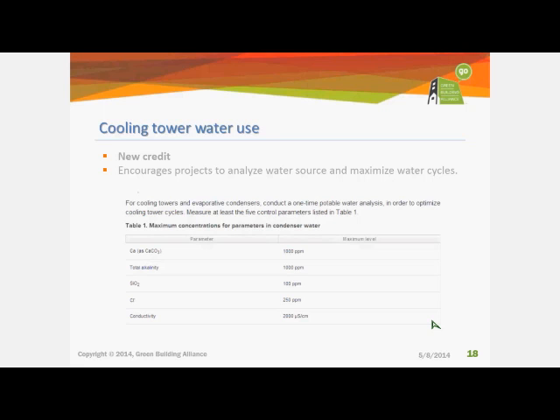Cooling tower. Here you're encouraging projects to analyze water source and maximize water cycles, so cooling towers aren't using once-through cooling, right — they're cycling through several times, reusing that water. For cooling towers and evaporative condensers, you conduct a one-time potable water analysis to optimize cooling tower cycles and measure at least 5 control parameters listed in Table 1.